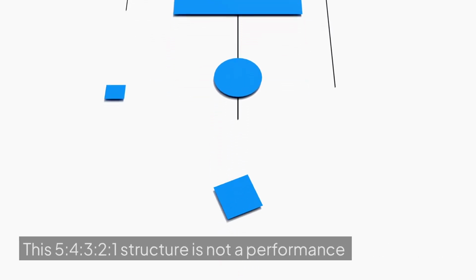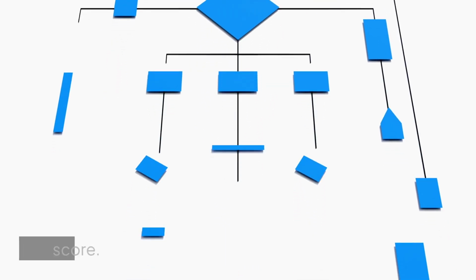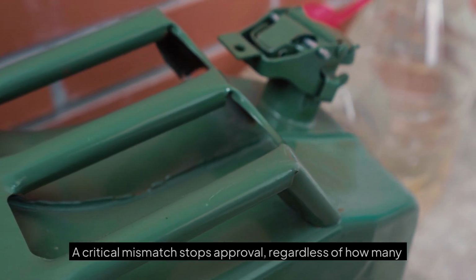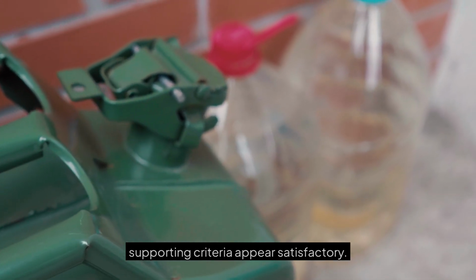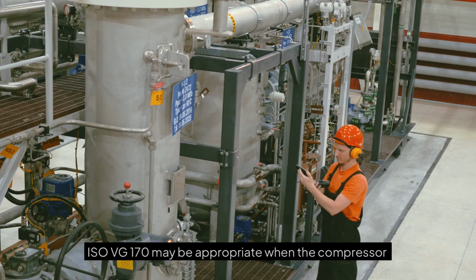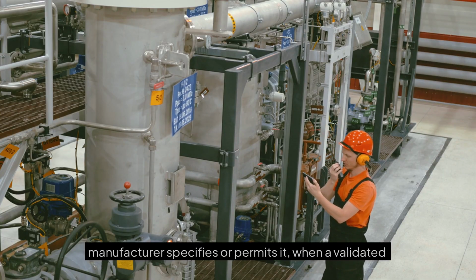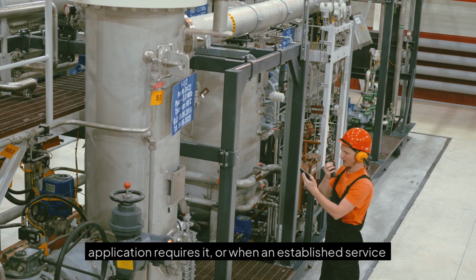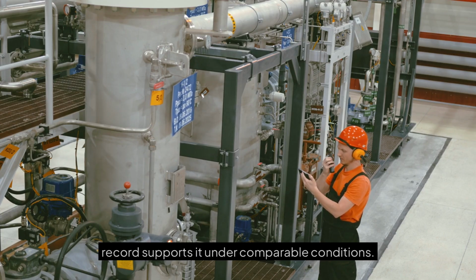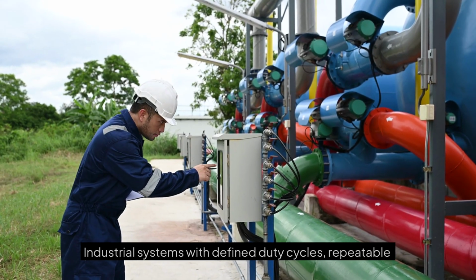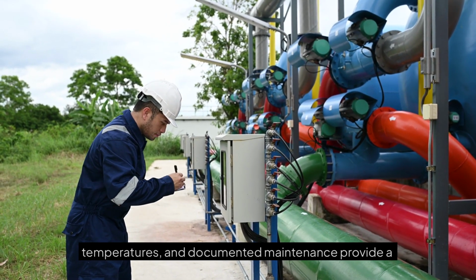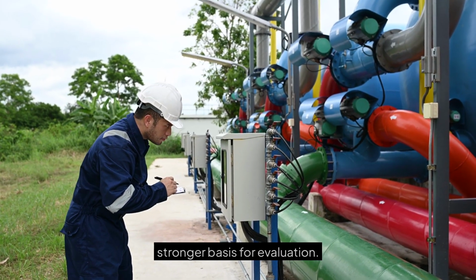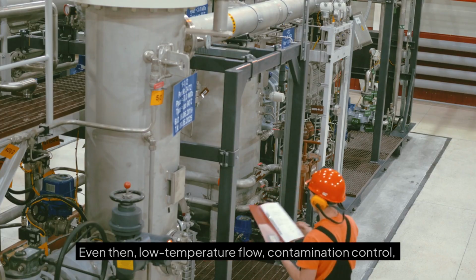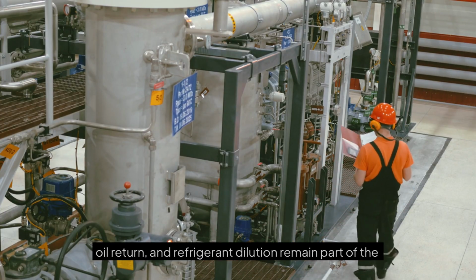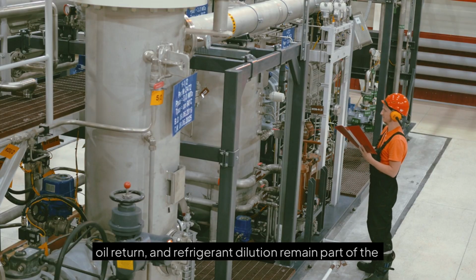This 5-4-3-2-1 structure is not a performance score. A critical mismatch stops approval, regardless of how many supporting criteria appear satisfactory. ISO VG 170 may be appropriate when the compressor manufacturer specifies or permits it, when a validated application requires it, or when an established service record supports it under comparable conditions. Industrial systems with defined duty cycles, repeatable temperatures, and documented maintenance provide a stronger basis for evaluation. Even then, low temperature flow, contamination control, oil return, and refrigerant dilution remain part of the decision.